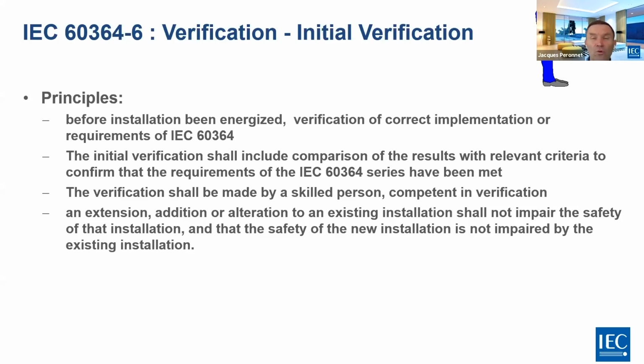Regarding initial verification, the principles of this initial verification are the following. It has to be made before the installation is energized, and we are going to verify the correct implementation of the requirements of IEC 60364. So this initial verification shall include a comparison of results with the relevant criteria to confirm that the requirements of the IEC 60364 series have been met. The verification shall be made by a skilled person competent in verification. And an extension, addition, or alteration to an existing installation shall not impair the safety of that installation, and the safety of the new installation shall not be impaired by the existing installation.